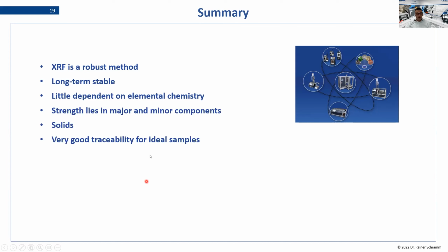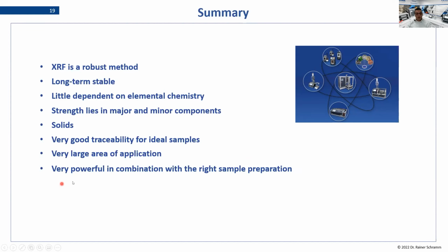We have a very good traceability if we have ideal samples like our fused beads. That means you could easily also create secondary standards and make your own calibrations when there are no CRMs available. And this is a very large area of application, and it's very powerful if, of course, you use the right sample preparation. And like always, there should be some experience involved.